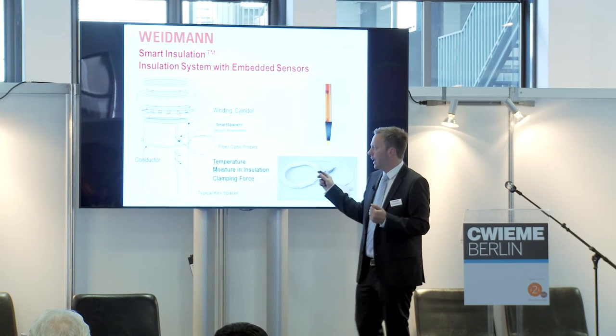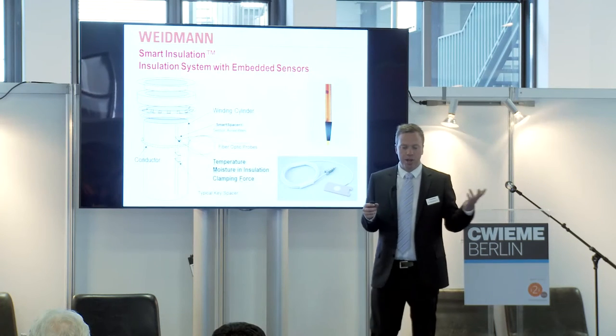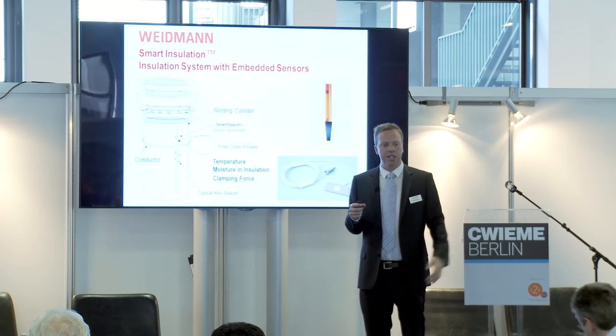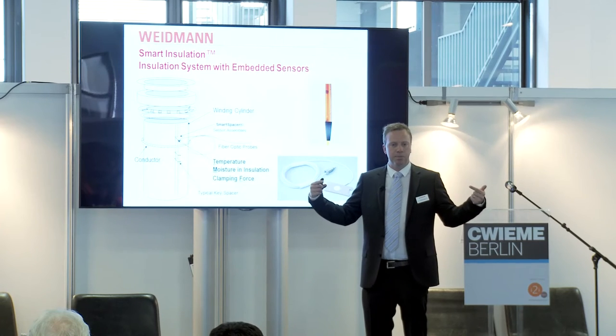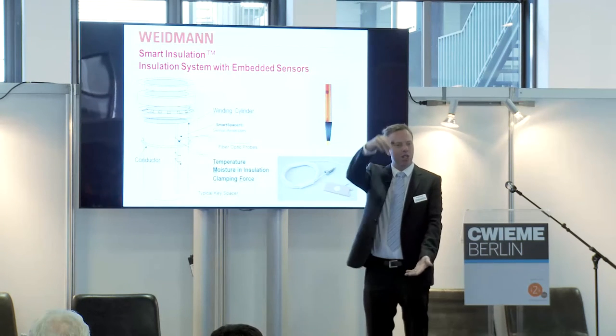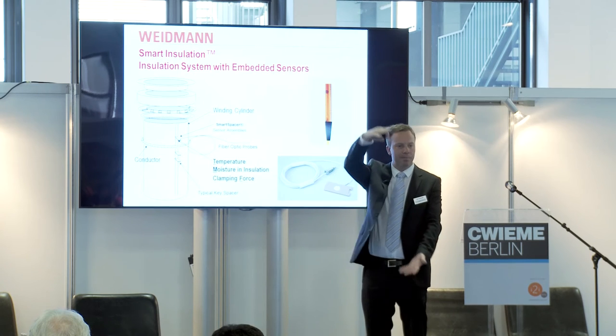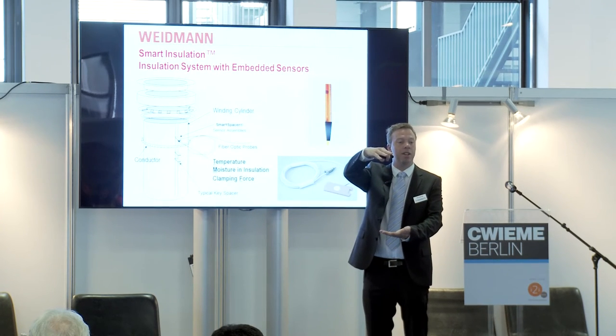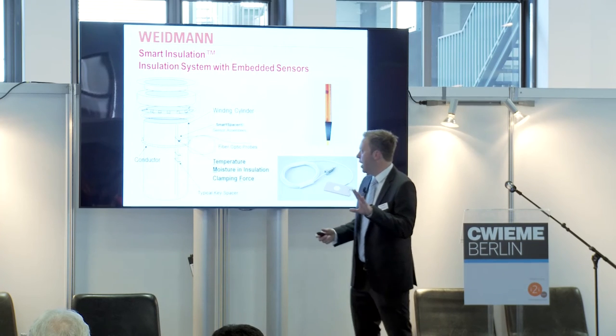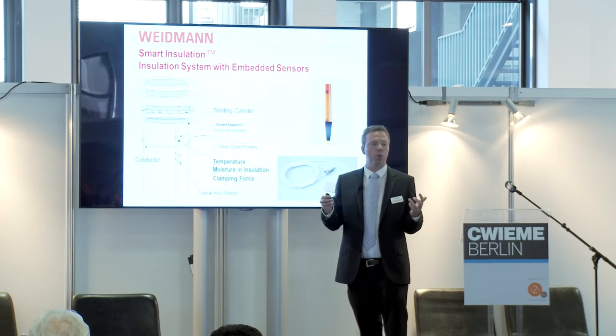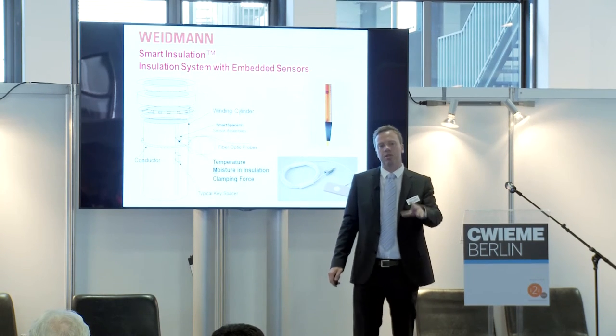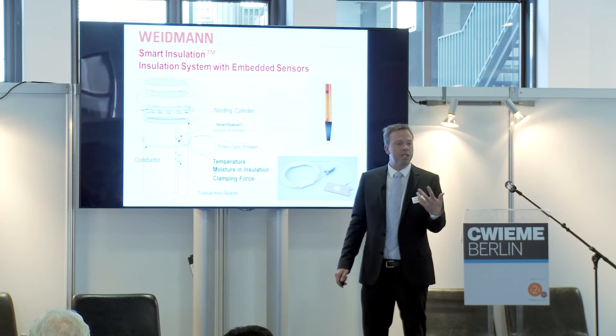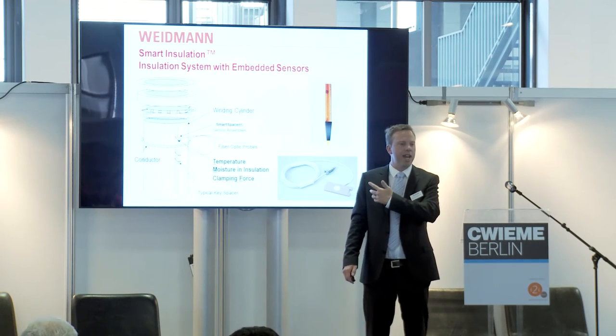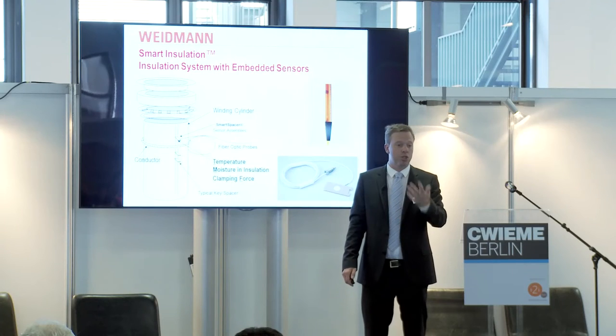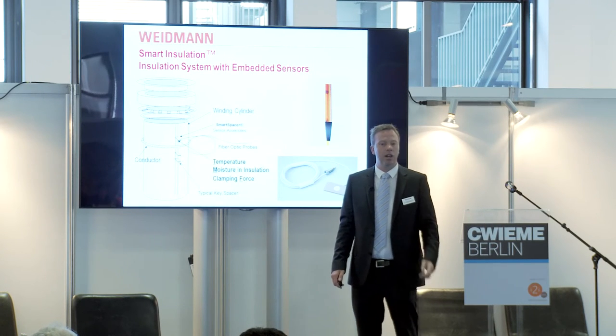Then finally, clamping force. Again, we've just registered a patent on this technology. We're using the spacers in the transformer to actually measure, by winding, the clamping force on that particular winding of the transformer. And these three areas we believe are somewhat unique as a package, and also something that, speaking to our OEM customers, whether it be ABB or Siemens, they honestly agree that they don't have a full understanding of these parameters.